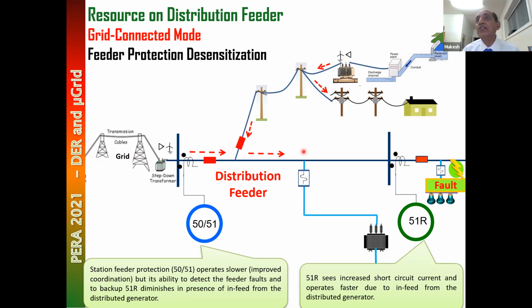That's not acceptable. You need to either desensitize this protection or do something else. You need to put another recloser in between here, which will provide a backup to this. If you provide a recloser here, now you have no risk. That recloser is seeing the total current, so there is no desensitization. So that's the decision you have to make. Do you need to put another recloser, another protection device here, which will provide a backup to this, and this will then provide backup to this? Those are the decisions you need to make.